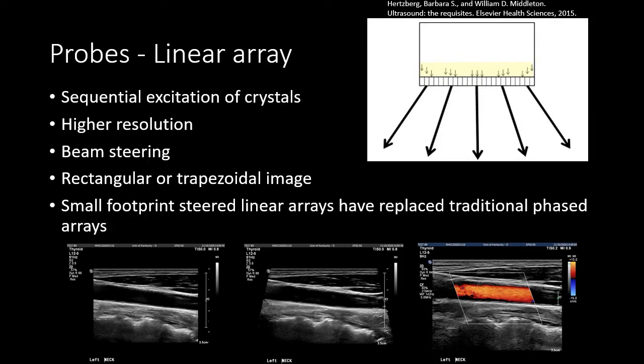A linear array probe is what we traditionally use for high resolution imaging of superficial structures. Unlike a phased array, the crystals do not all excite at the same time — there is sequential excitation of the crystals, which results in higher resolution. Pulses generated by the linear probe can be angled or steered to create rectangular or trapezoidal imaging. Small footprint linear arrays have in many instances replaced traditional phased arrays because of their better resolution, and we often use these for superficial imaging like the neck or extremities.